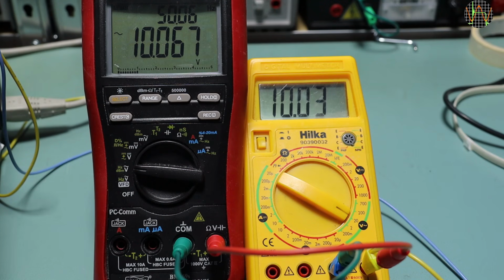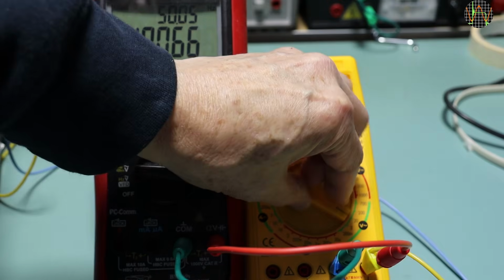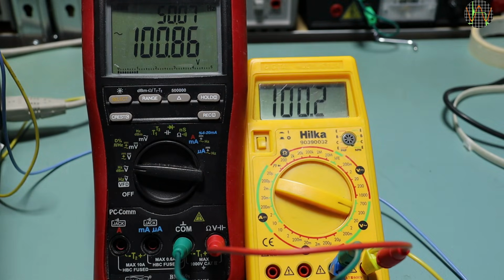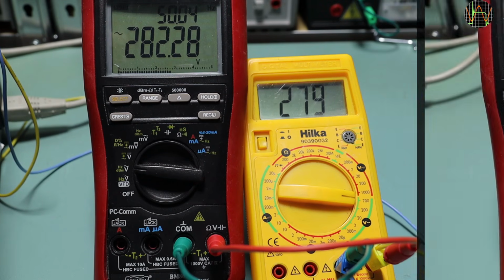For higher AC volts, I use a mains powered variac. 10 volts in the 20 volt range, quite close, 100 volts in the 200 volt range, okay, and 200 volts. Switching to the 700 volt range, 282, and the Hilka is just 1.1% out. That is well within spec of similar meters, no problem with AC volts.